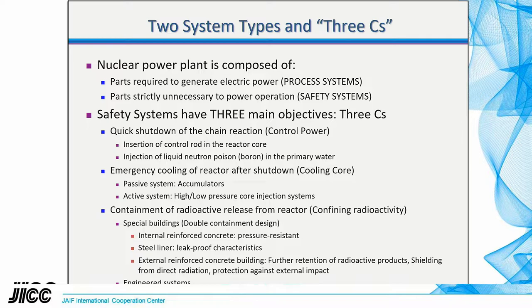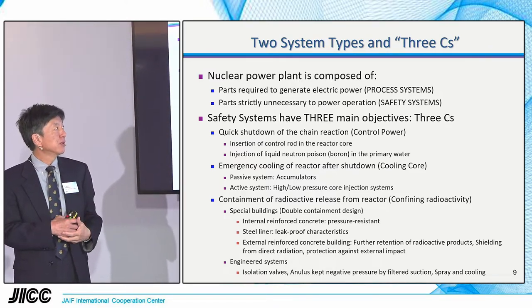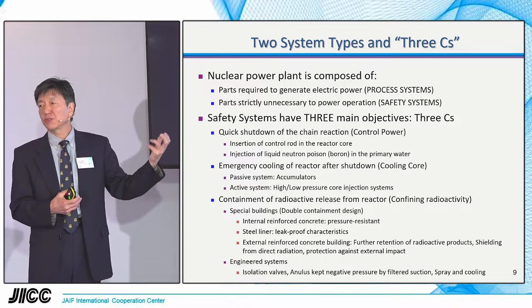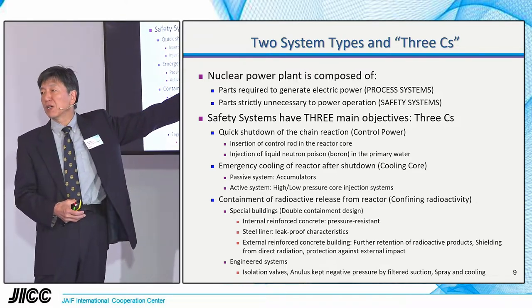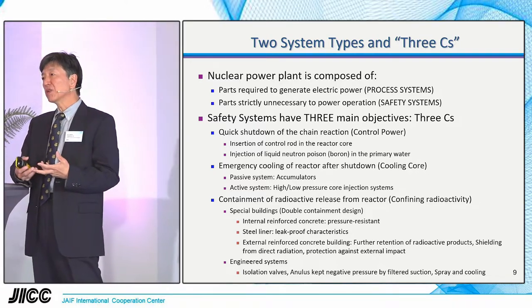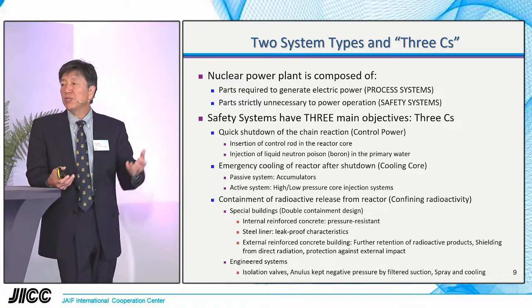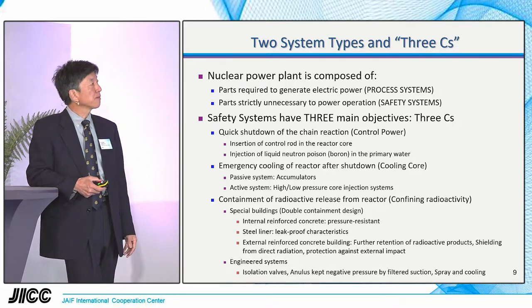The first C is control power — the quick shutdown of the chain reaction. This is achieved by insertion of control rods in the reactor core, or reactor SCRAM. The second method is injection of liquid neutron poison — usually boron is used. This poison is put into the primary water, circulates the reactor system, and since boron is a good neutron absorber, the reactivity in the reactor core is reduced, meaning reactor power decreases.